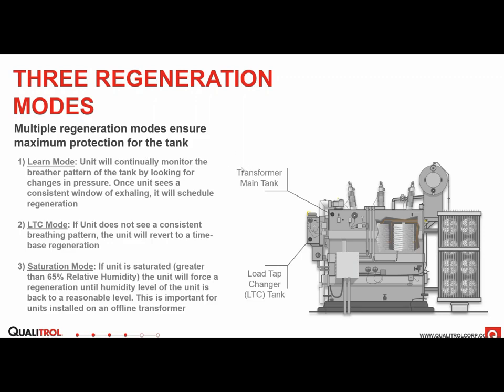So we have 3 regeneration modes with the new breather. We have learn mode, which we just discussed. It'll sense for the continuous exhale phase over a certain time period, and once it needs a regeneration, it will wait for that time and regenerate in that window. LTC mode is when the breather doesn't sense a consistent breathing pattern, and the breather will revert to a time-based regeneration. And then saturation mode is if the silica gel is very saturated, so the humidity level goes above a certain point, it will regenerate as soon as possible.